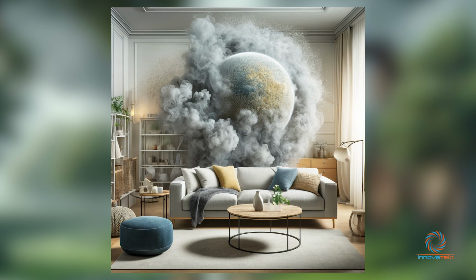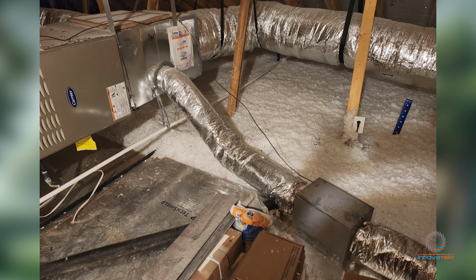If this device is bringing hot, humid air into your house during a rainy day, imagine what happens: it rains, the temperature drops, so your air conditioning system doesn't run that much. Since it doesn't run that much, this fresh air device notices it's set up to bring in X amount of fresh air during the day, so it opens up and starts bringing in hot, humid air from outside. Your AC isn't running as often since it's not that hot, so it gets more humid inside your house. Configuring this device with your air conditioning system is very important.